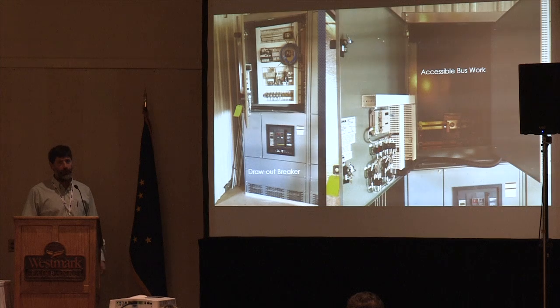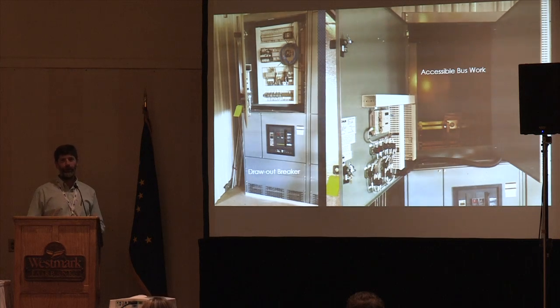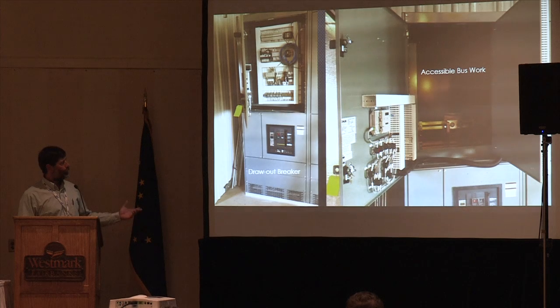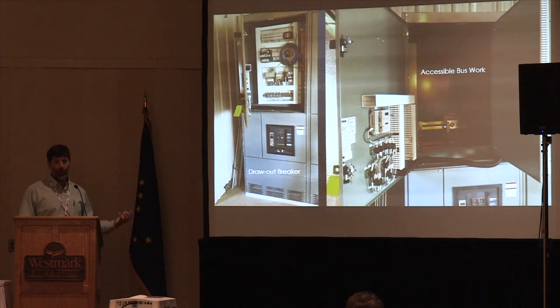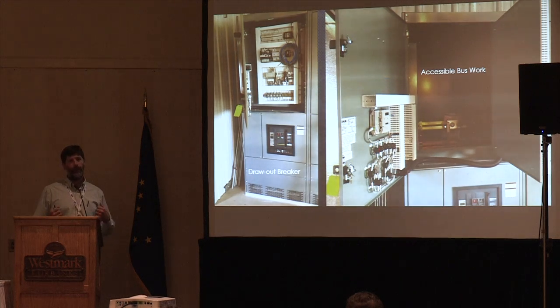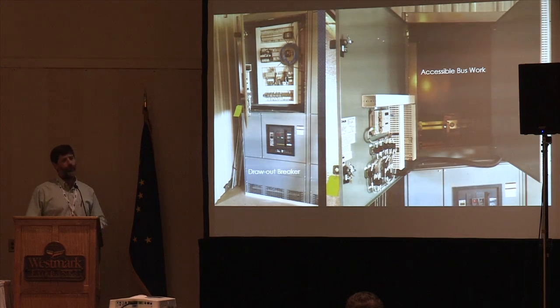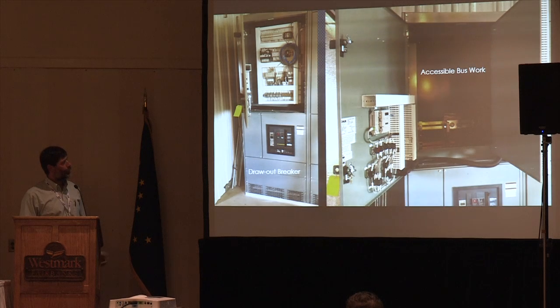We've noticed that when we put in these automated switchgear, a lot of times the size and constraints don't let you get behind the gear if you have to do any changing connections to the buswork, that sort of stuff. So we've gone to what you call a draw-out breaker. This whole panel will pull out. If you have a bad breaker, you can pull that panel out, disengage it, fix it, and put it back into place. You don't have to crawl around behind the back of the panels, and the buswork is accessible. This panel actually slides out, and you can see the buswork behind there.